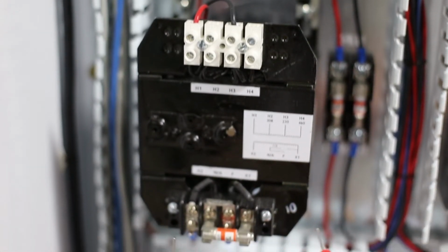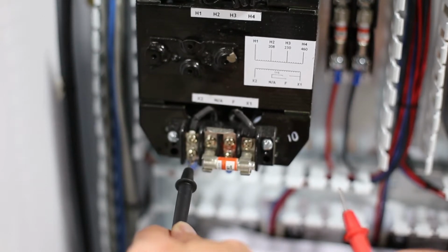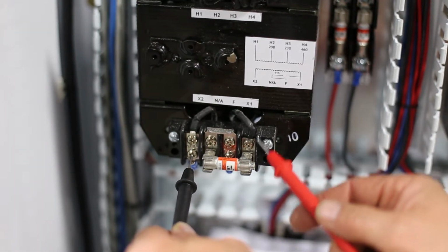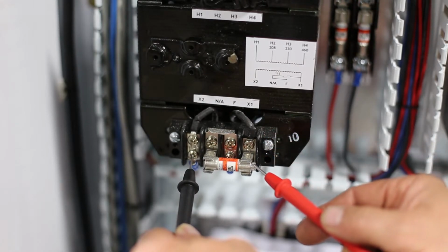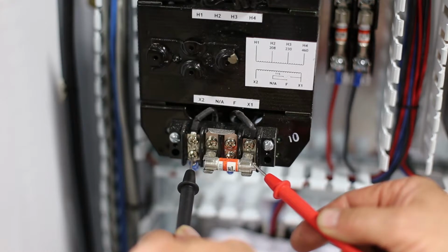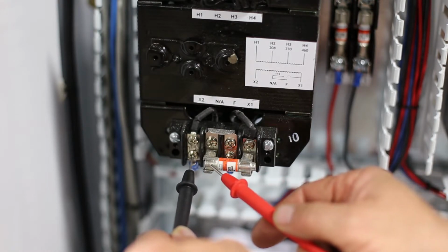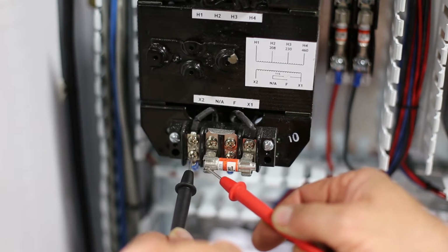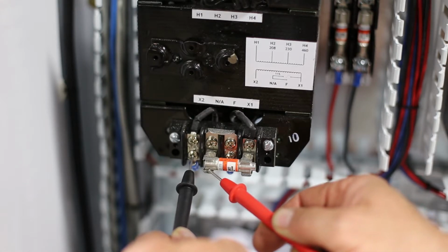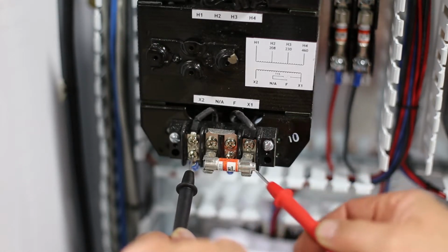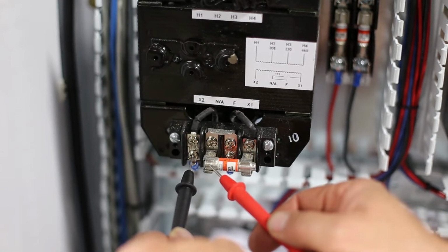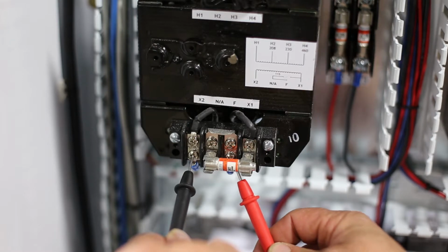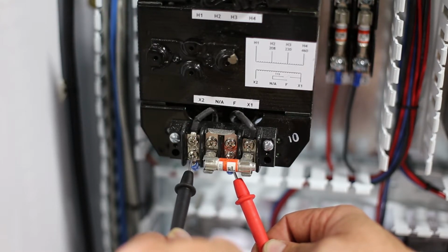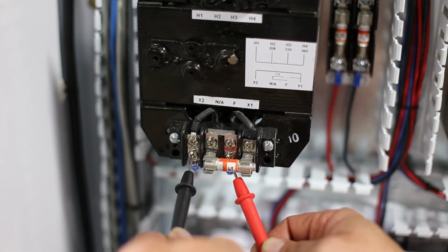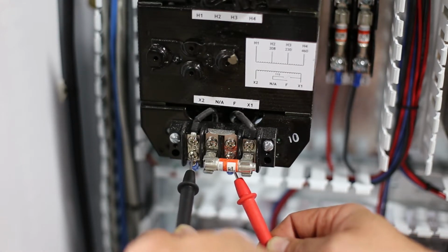On the output side of our transformer, over here on the far left is our neutral. Over here on the far right is where the power comes out of the transformer into the fuse. So we check there and we should have about 120 volts AC. Then we check over to the left side of the fuse, and that is the output side of the transformer on the fuse side. If you have 120 volts there, that fuse is good. If we do not have power there, we have to replace this fuse. Once the power goes through this fuse, it goes to 1A, which is a wire behind this fuse that goes out to the gray terminal blocks where our control circuit begins. So in this case, we have 120 volts, so this transformer is good.